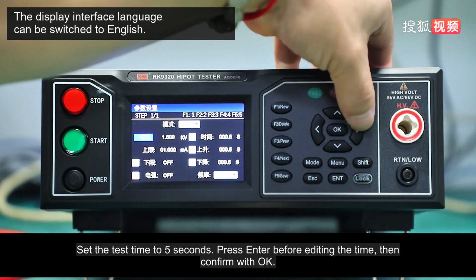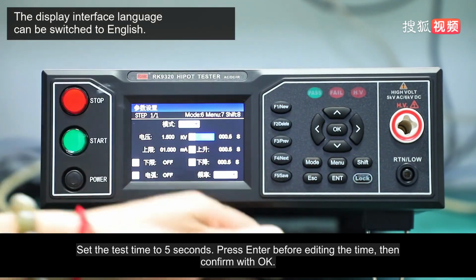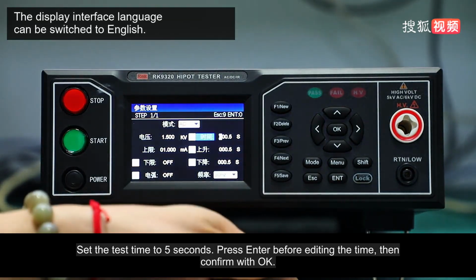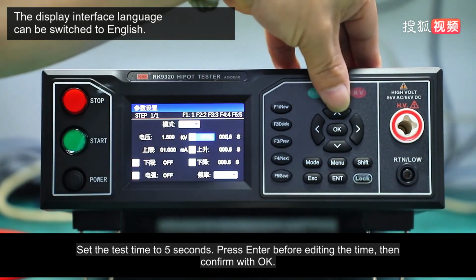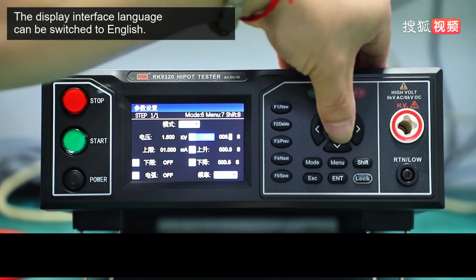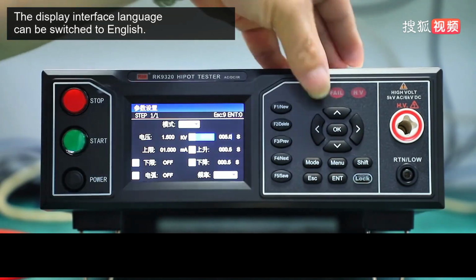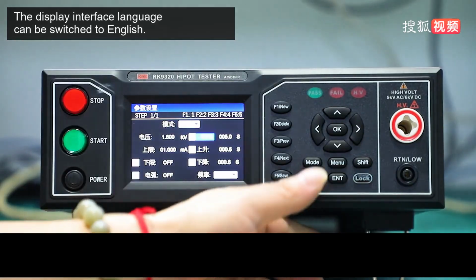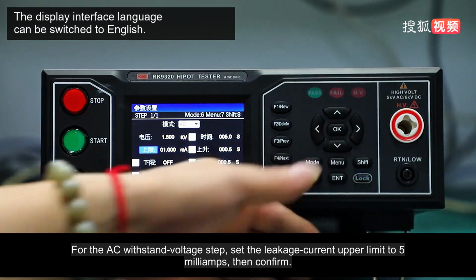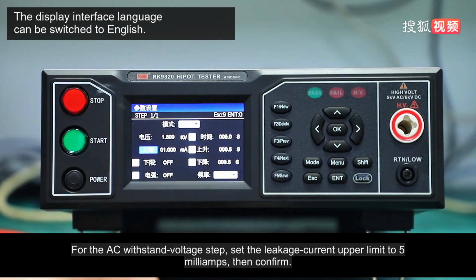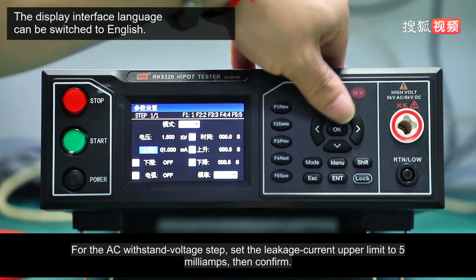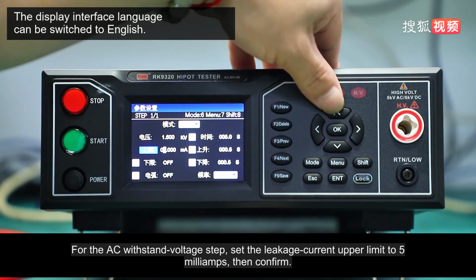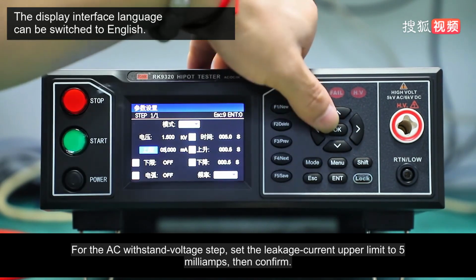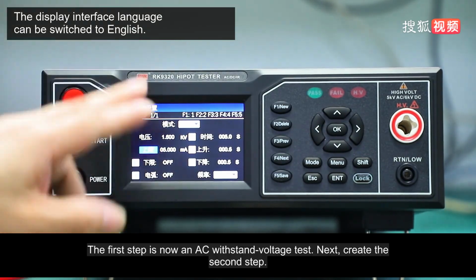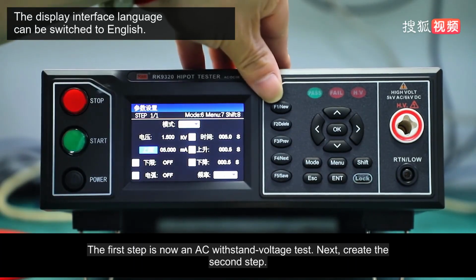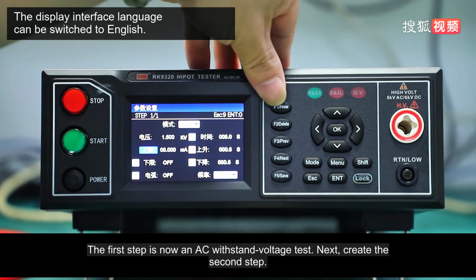Set the test time to 5 seconds. Press Enter before editing the time, then confirm with OK. For the AC withstand voltage step, set the leakage current upper limit to 5 mA, then confirm. The first step is now an AC withstand voltage test. Next, create the second step.